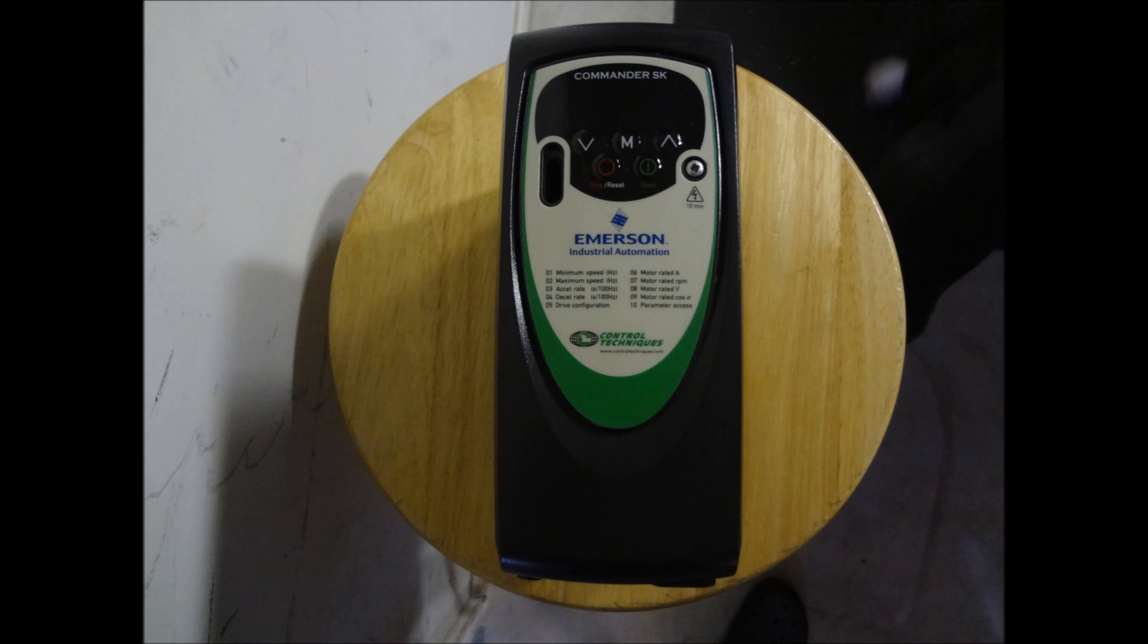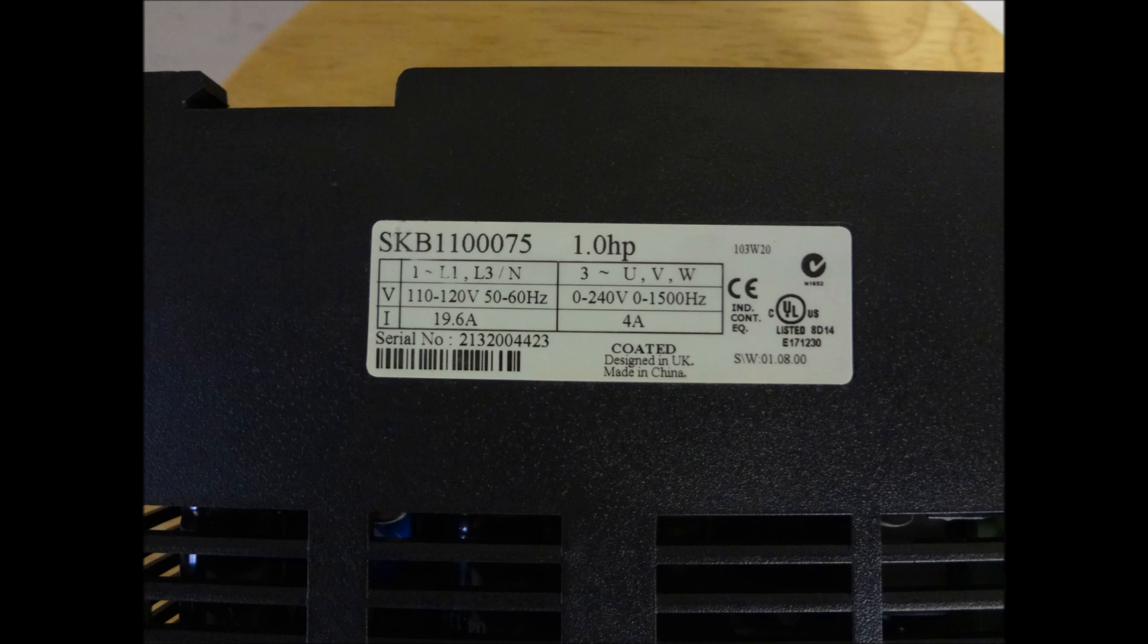It's a good drive but I found out that you can't just directly hook a braking resistor to that VFD. You have to have a special braking module and I think it was like 130 dollars for this braking module.